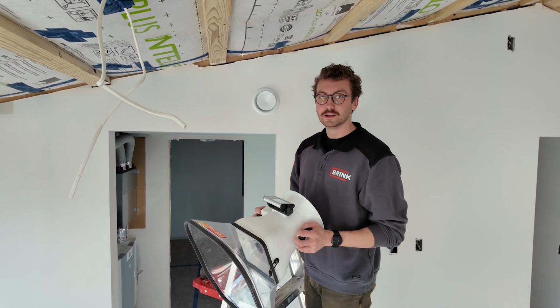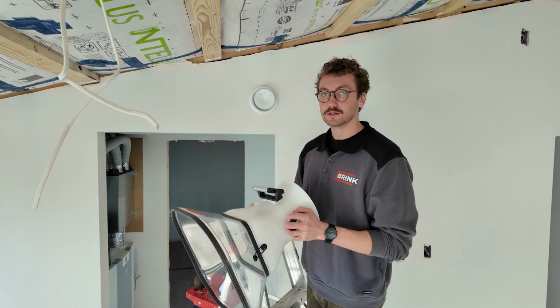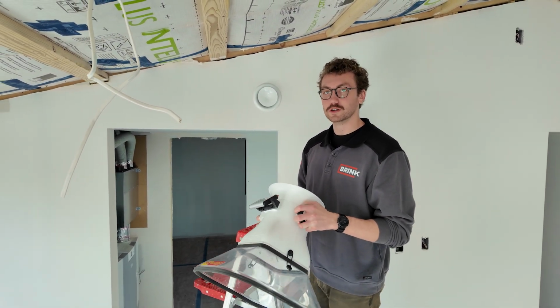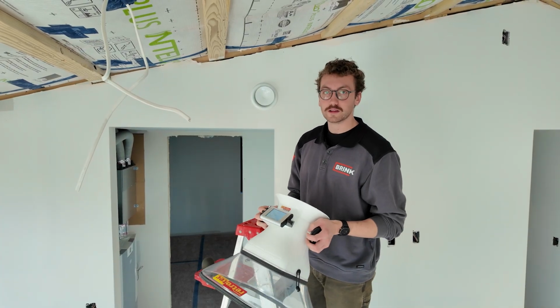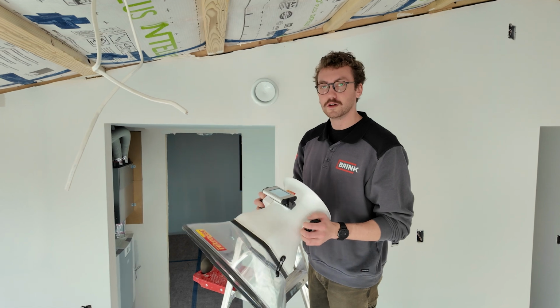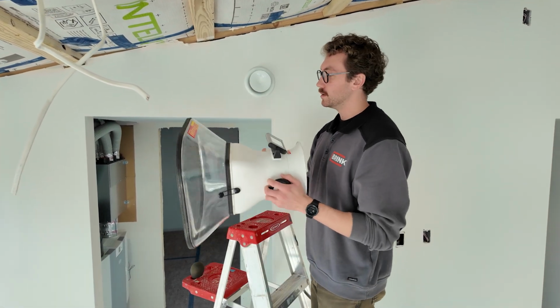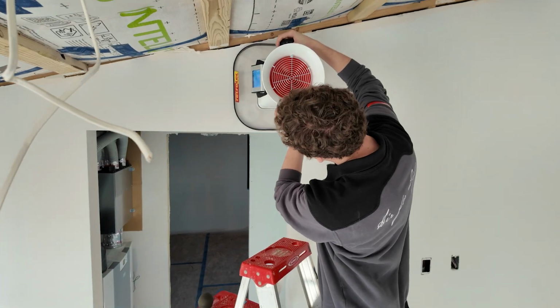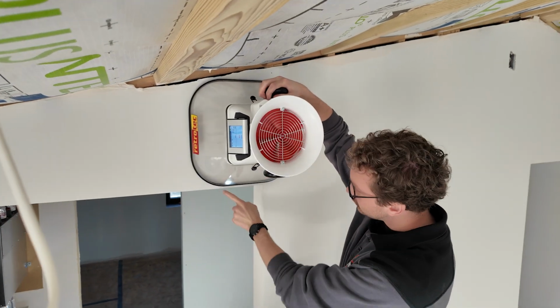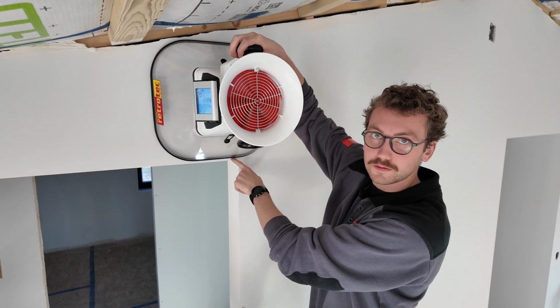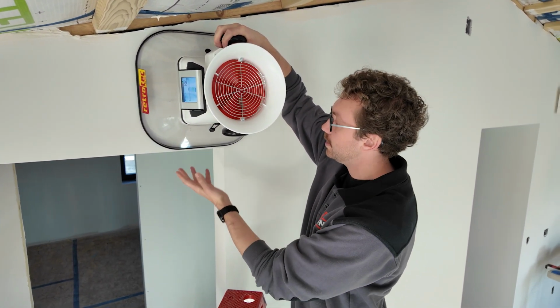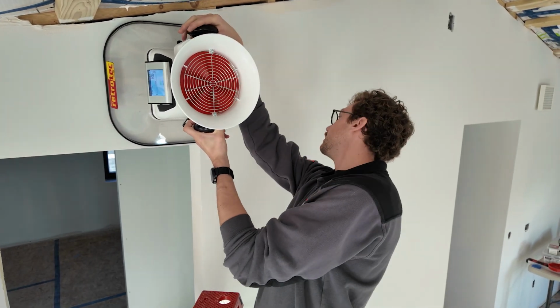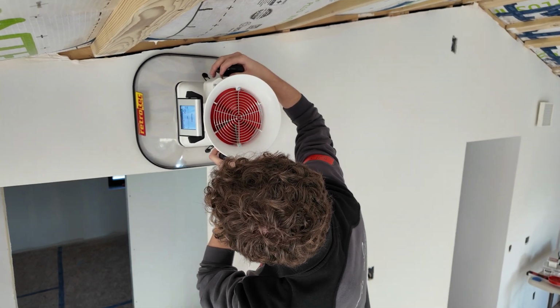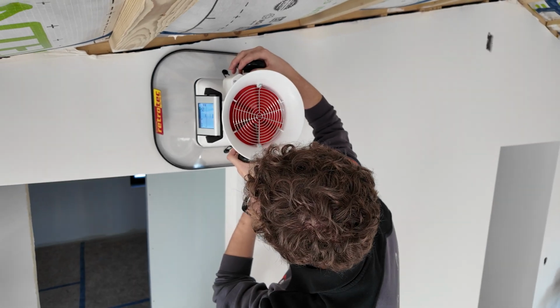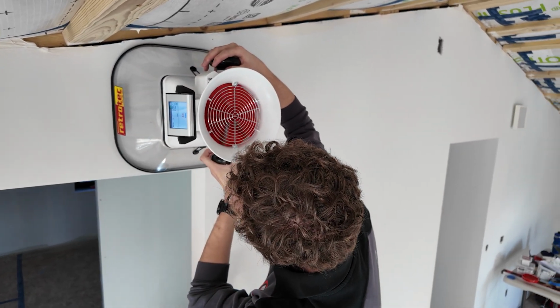So now that everything has been verified to be installed correctly, we've got the right unit, we now turn the unit on, program the flow rates, and we're ready to measure the flows in all the rooms. Here we're in the living room looking at our supply. We're going to use the Retrotec FlowFinder to check for 15 CFM. As I place the flow finder over the diffuser, I get it centered on the diffuser as best I can, and I make sure to not have any gaps where the hood is overlapping and getting some extra air or losing some pressure. So now that it's placed nicely on here, we'll press the button to go into stabilizing mode, and we'll start reading what we're getting out of here. So it's measuring that it's a supply, which is what we want to see.